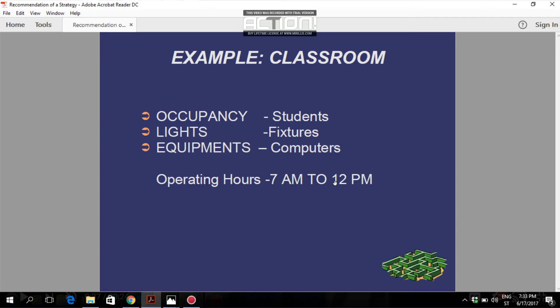For the remaining hours, HAP is not going to consider any load due to these three components. This means we can get the accurate heat load hour by hour — that's why this program is called the Hourly Analysis Program. In this case, heat load is calculated only for five hours, which leads to a lesser cooling load, a smaller equipment size to be selected, and cost reduction. That's why these profiles are so important.